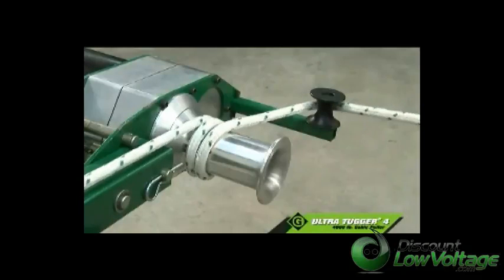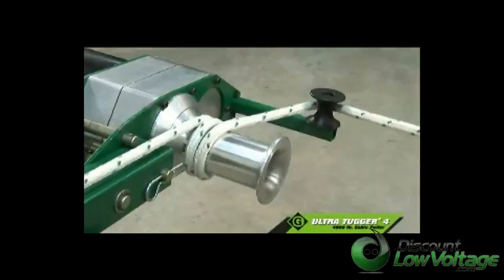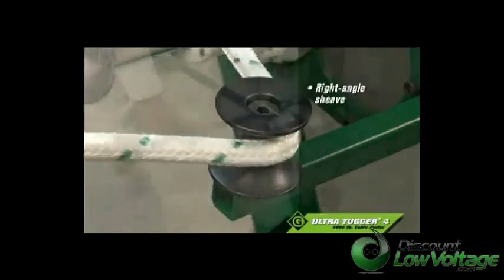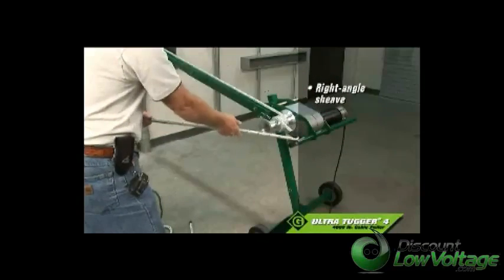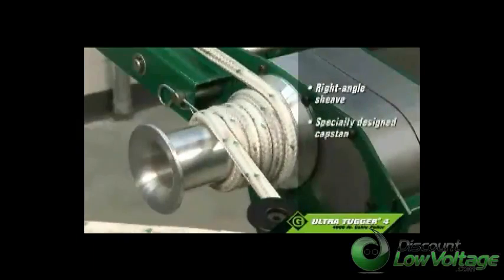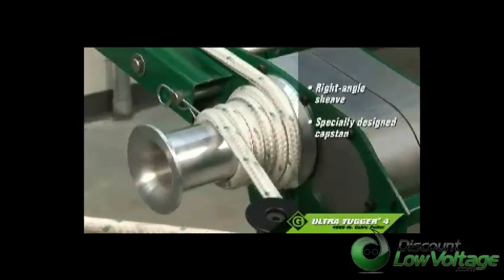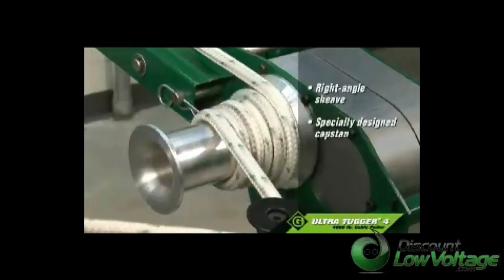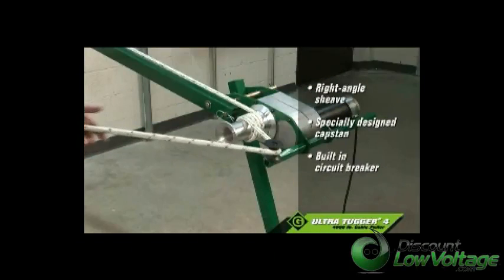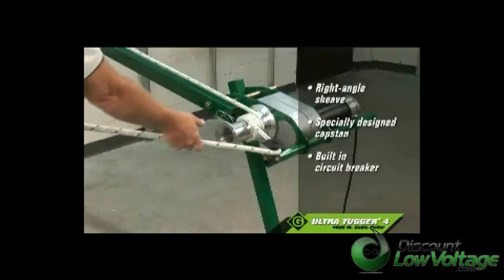The UT-4 has several standard safety features that protect the operator during the pull. The right-angle sheave positions the operator away from being in line with the pulling rope and cable during a pull. The special design of the capstan helps to prevent the pulling rope from overlapping. And the motor has a built-in circuit breaker to protect the motor and prevent puller overload.